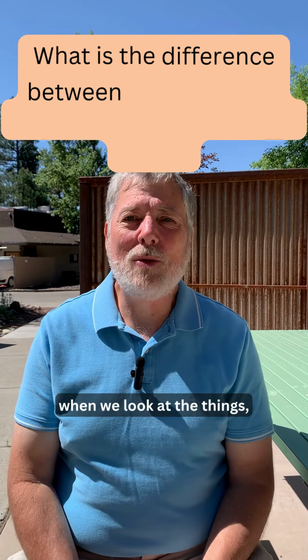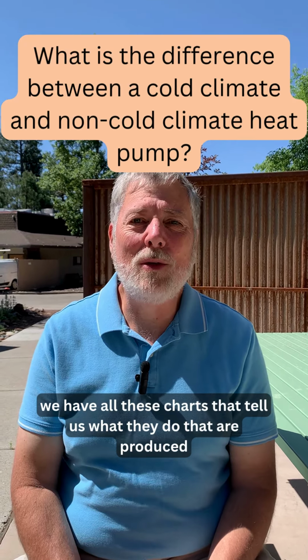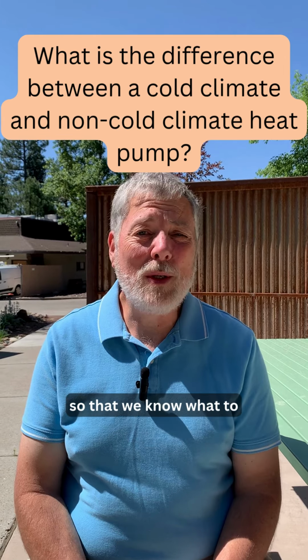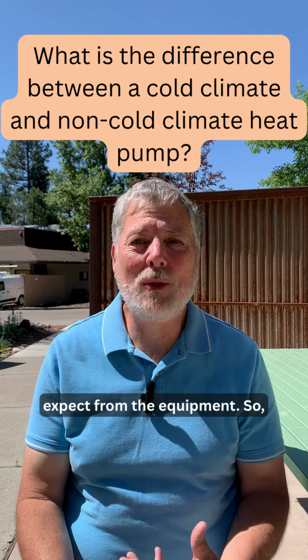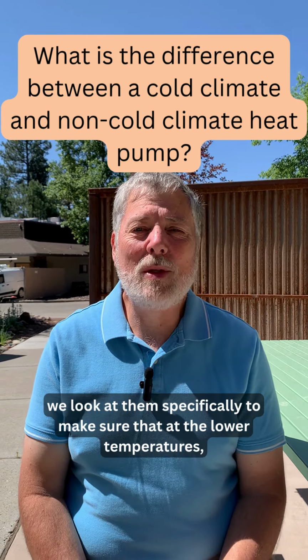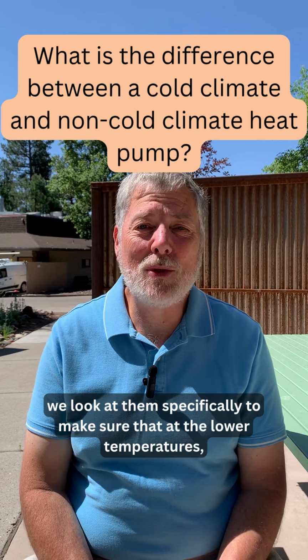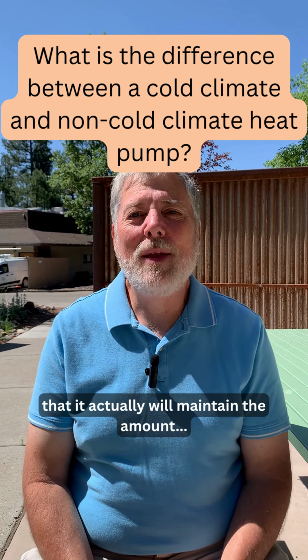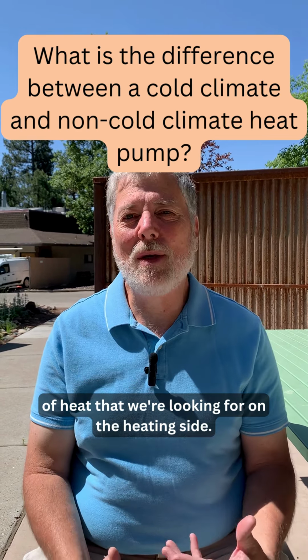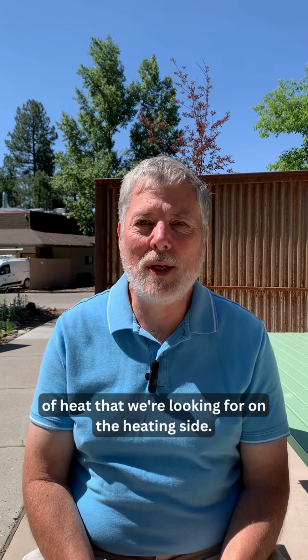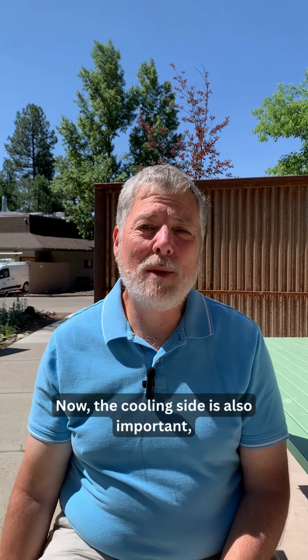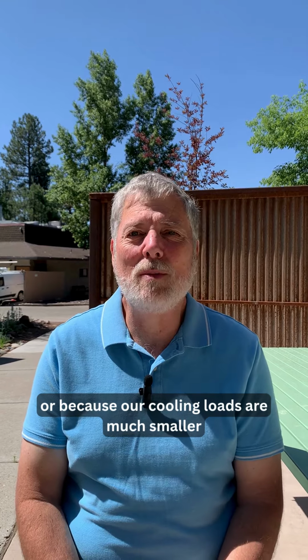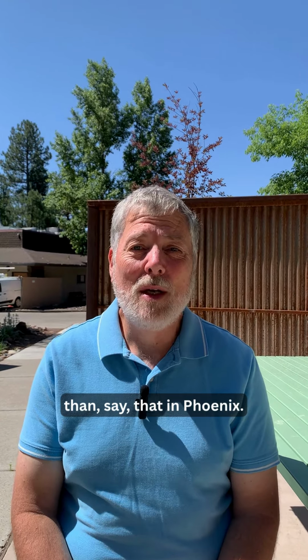So when we look at the charts that tell us what the equipment does, produced by the manufacturer, we know what to expect from it. We look at them specifically to make sure that at the lower temperatures, like we have here in Flagstaff, it will actually maintain the amount of heat we're looking for on the heating side. The cooling side is also important, but it's not as critical at this elevation, because our cooling loads are much smaller than, say, in Phoenix.